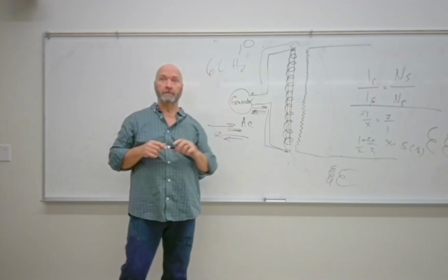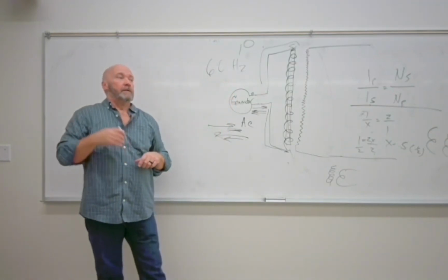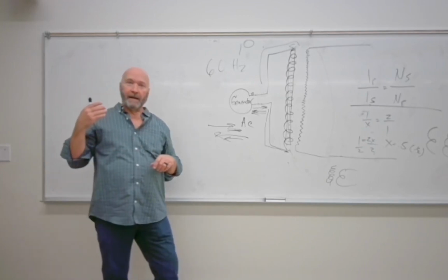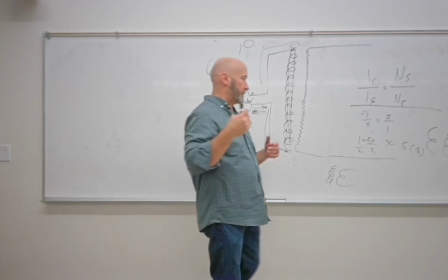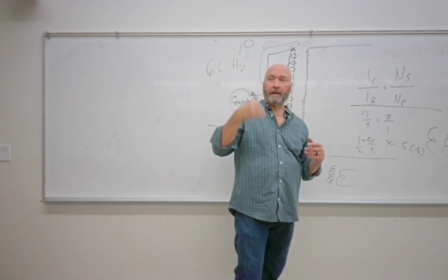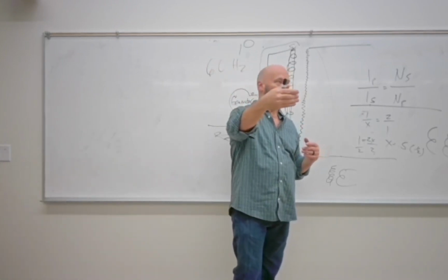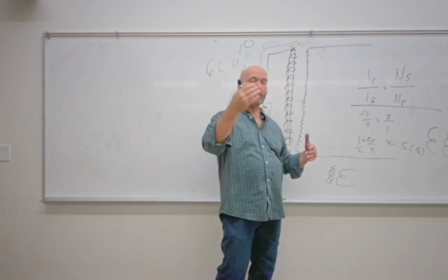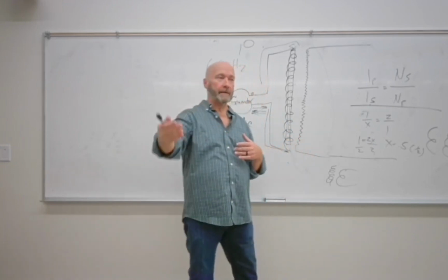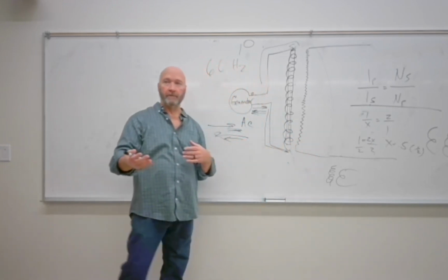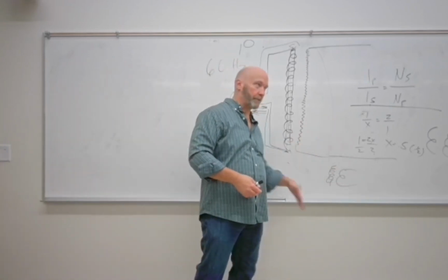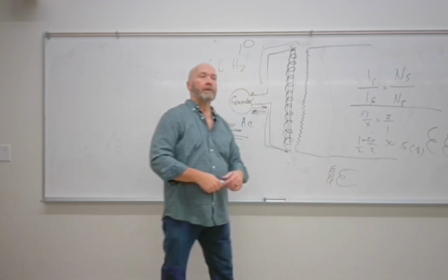It's very close, right? So what you don't want is to feed it 250 volts, or 240 volts as it were, because you might have electrons jump across before you're ready for them to go. Okay, so to heat the filament, what we want is very low voltage so they don't make that travel across the tube until we hit it with high voltage. So the purpose for the filament transformer is to reduce the voltage.